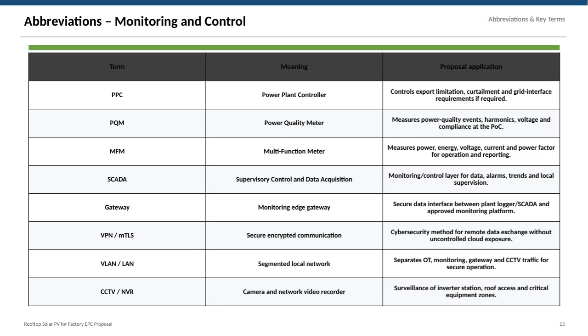Here we have some important abbreviations and key terms related to monitoring and control in our rooftop solar PV proposal. Starting with PPC, the power plant controller, which plays a crucial role in managing export limitations and ensuring compliance with grid requirements. Then there's the power quality meter, or PQM, that monitors events like harmonics and voltage quality at the point of connection. The multifunction meter measures key operational parameters such as power, energy, voltage, and current, helping with reporting and analysis. SCADA is our supervisory control system that handles data collection, alarms, and local supervision.